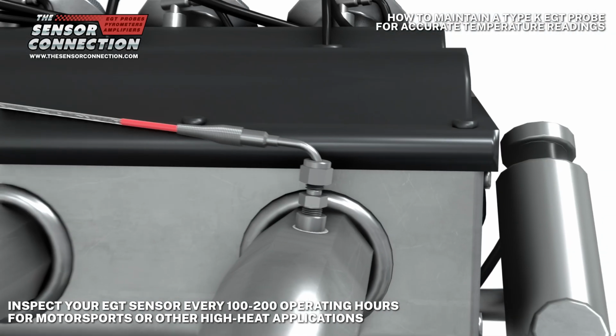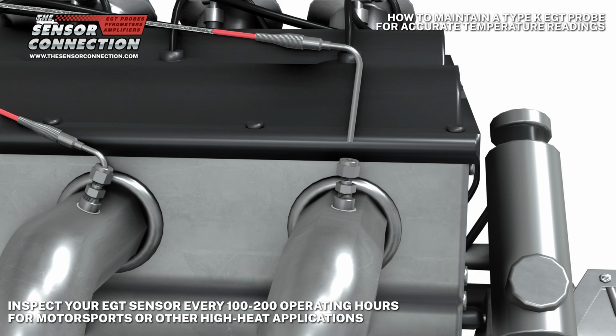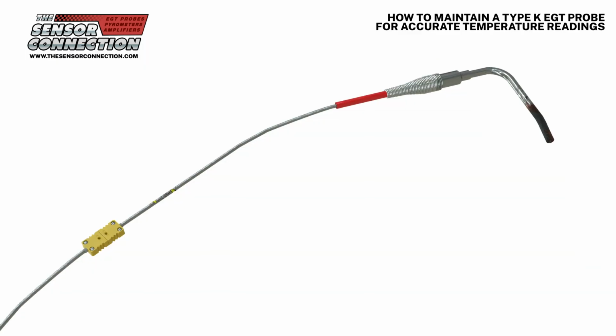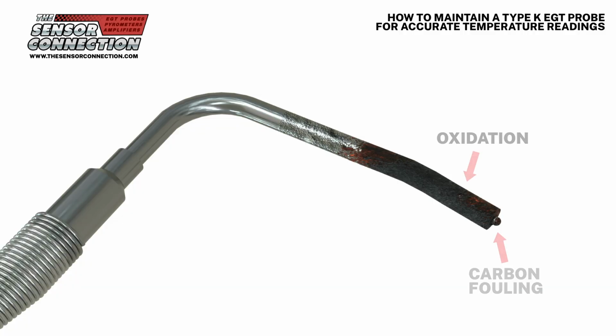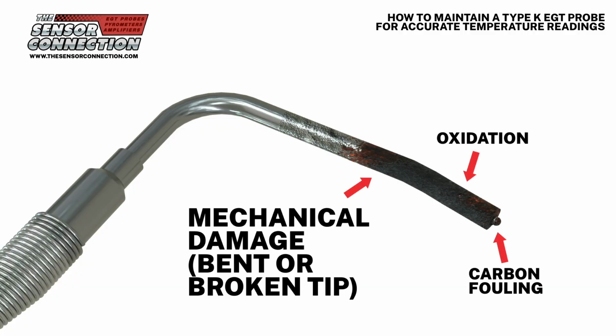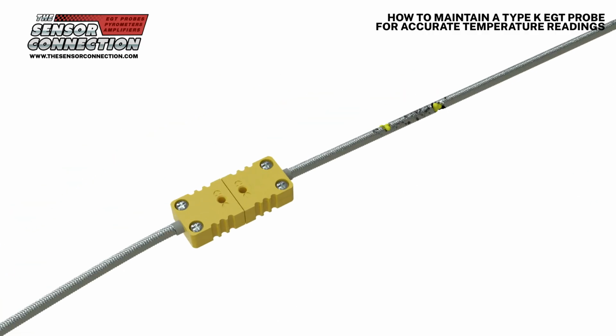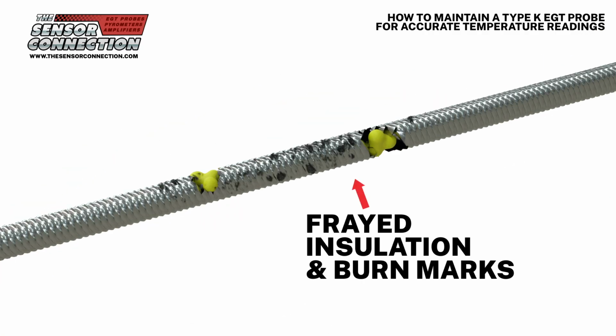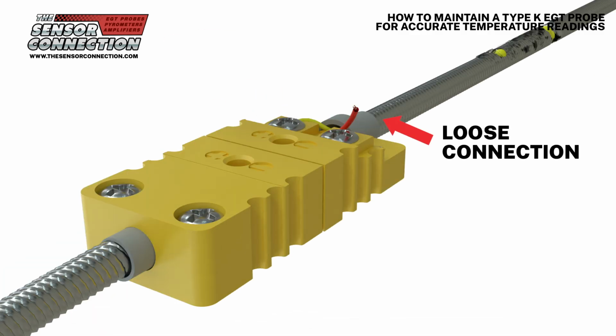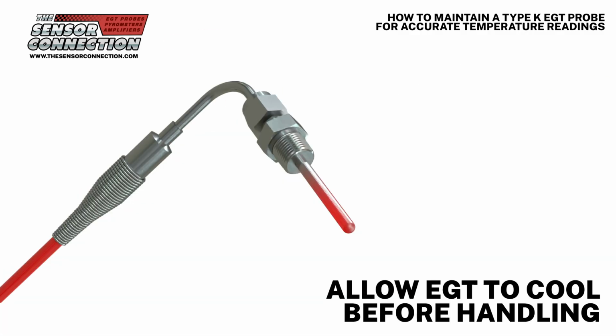For industrial engines, follow your normal service intervals, or inspect sooner if you suspect performance issues. Start with a visual check. Look for carbon fouling or oxidation on the probe tip. Check for mechanical damage like bent or broken tips. Examine the sheath for signs of pitting. This could indicate overheating. Inspect the wiring for any frayed insulation or burn marks, and inspect the connectors for loose connections.